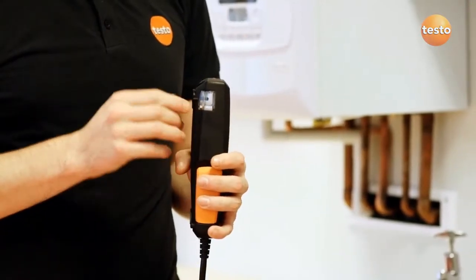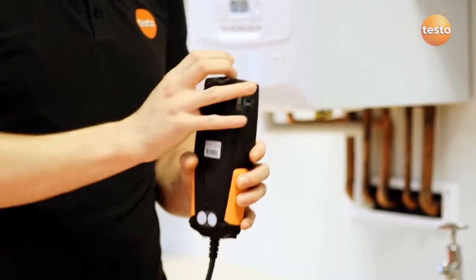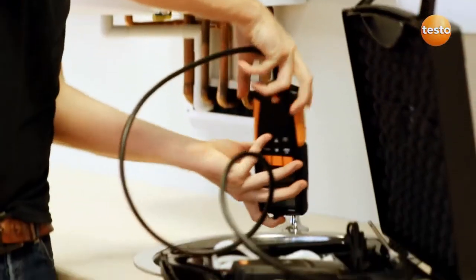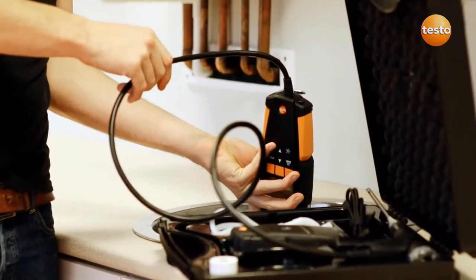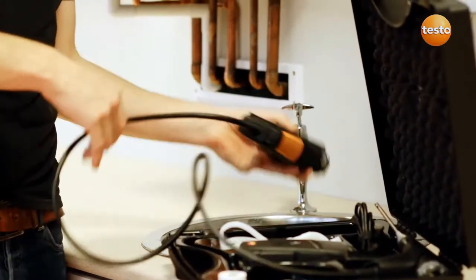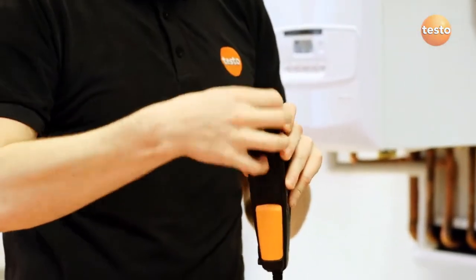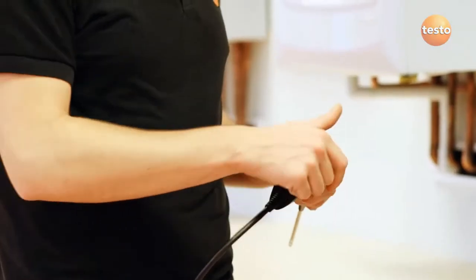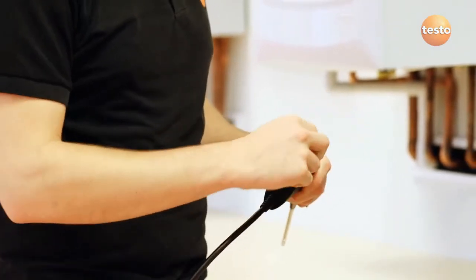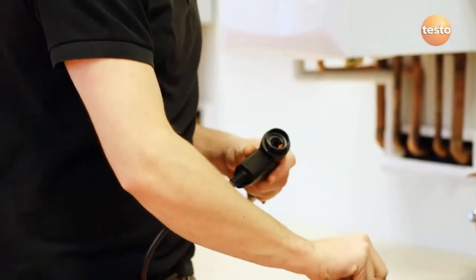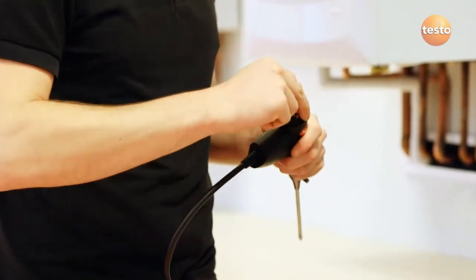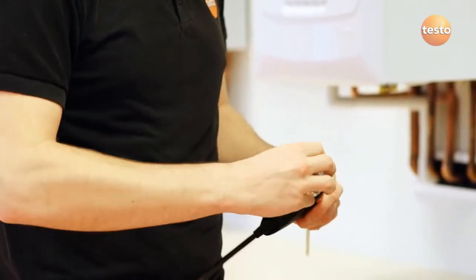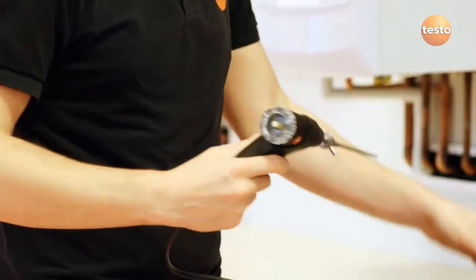Remember to always check and empty the condensate trap before measuring. Once empty, make sure the plug is pushed back in so there is no air leakage into the measuring instrument. Regularly check the filter on the probe handle, which is really easy to do on the 310. If the filter is dirty, then throw it away for a new one. If it's wet but clean, you can fit a dry one and keep the old one to dry out.